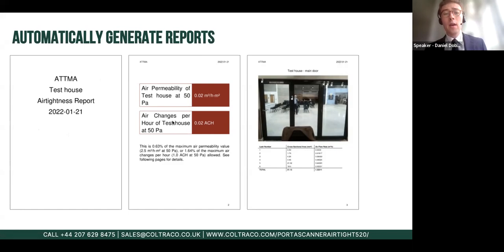Then we have a sort of summary page. Now this page tells you a value for the air permeability of that house in this instance, as well as the air changes per hour, which can be a useful metric for understanding how much air is going to move in and out of that space over a certain period of time. Each succeeding page after that summary page will show one of the structures that has been tested. In the first instance, it's the main door of the house that we tested here.